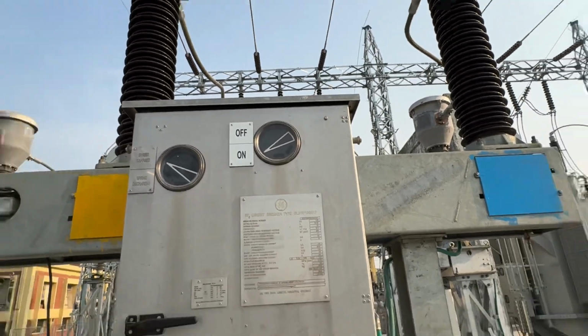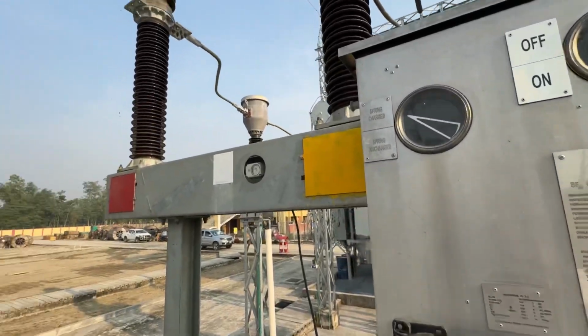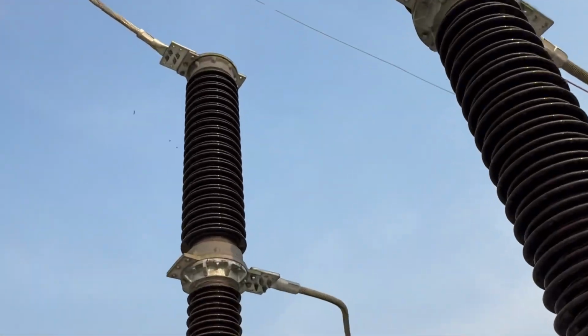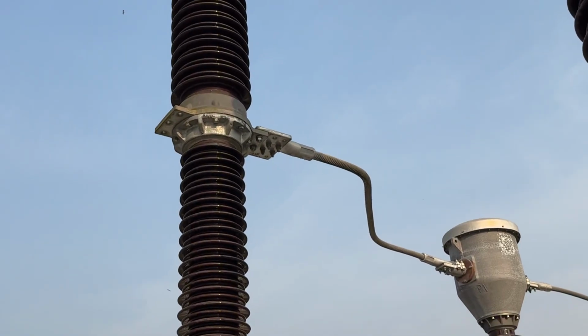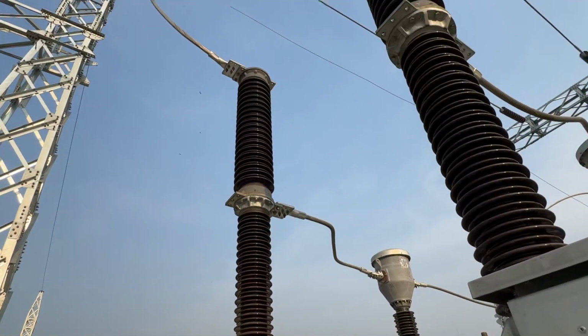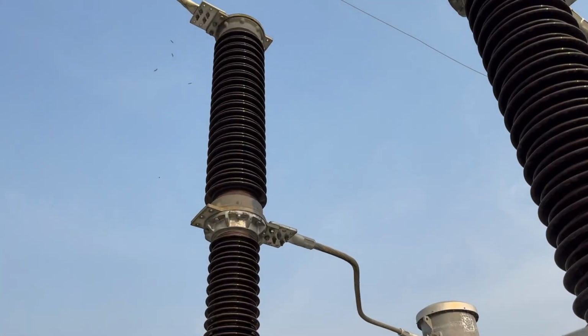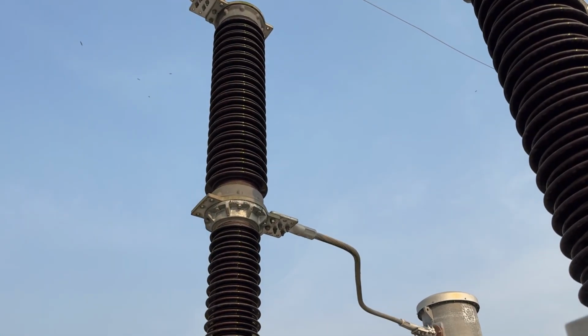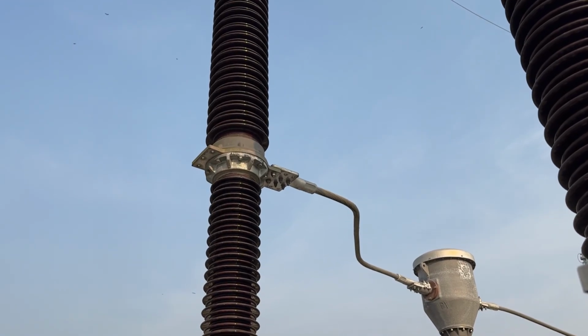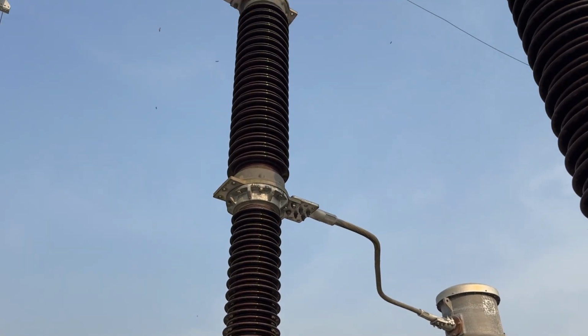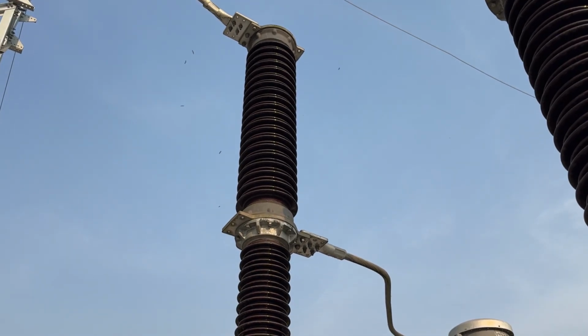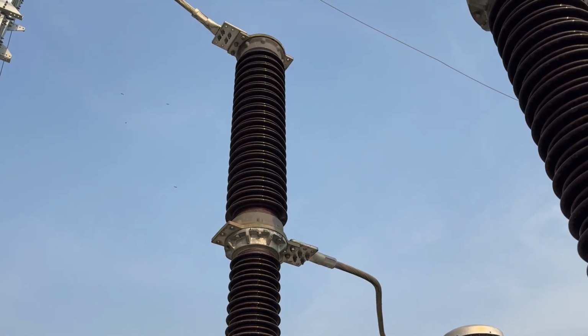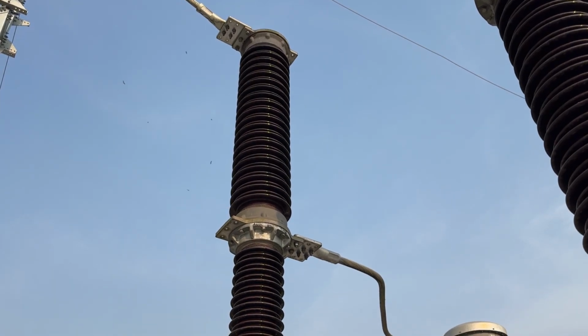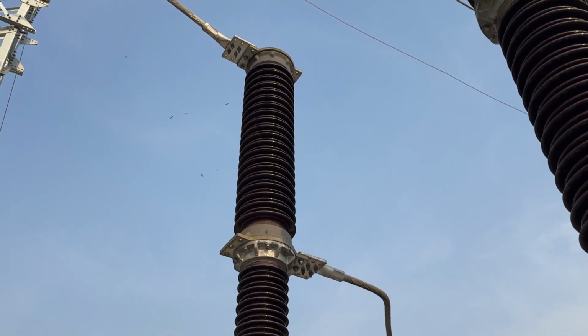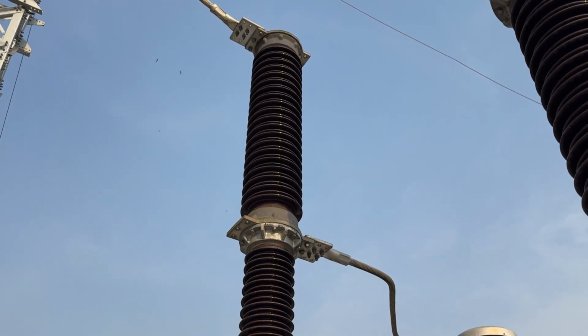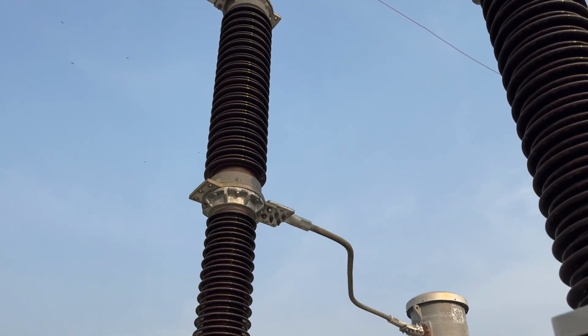This is the operating mechanism. The top connection is called the upper terminal, and the middle connection is called the lower terminal. The upper terminal is the source side. There is always voltage here, and at the lower terminal, when the breaker is closed, there is voltage here. Upper terminal and lower terminal are connected. When disconnected, there is voltage at the upper terminal, but no voltage at the lower terminal. There is a contact between these terminals inside the porcelain insulator.